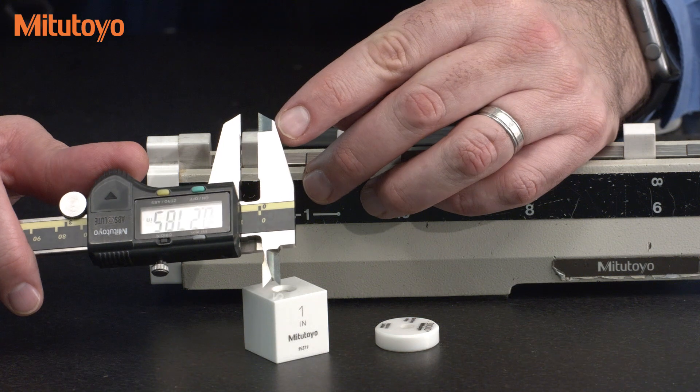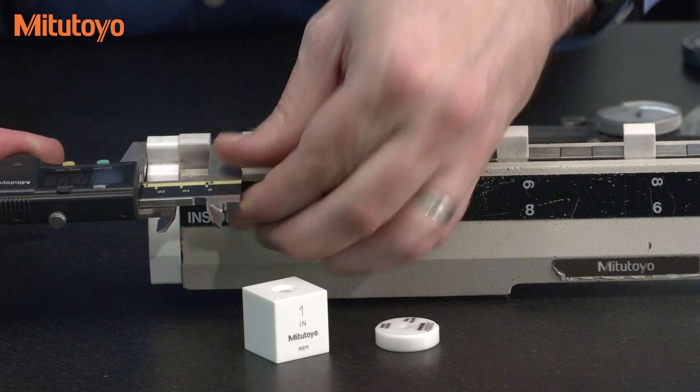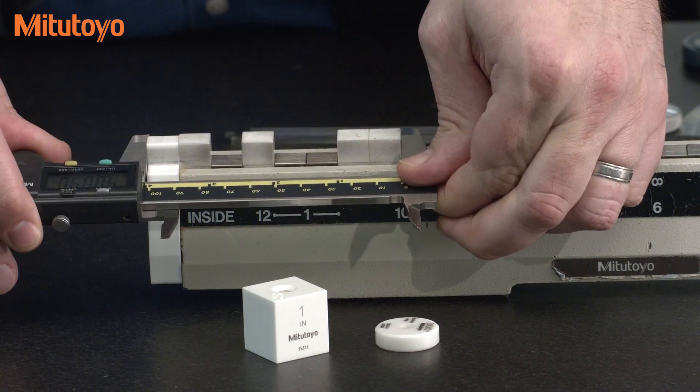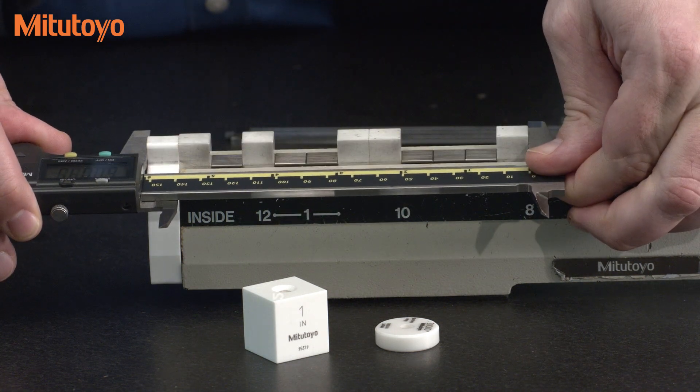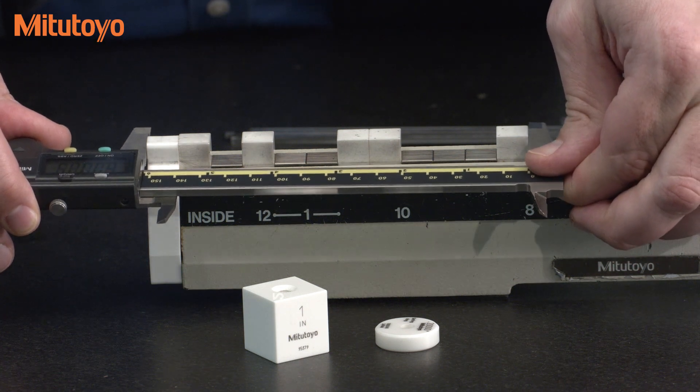For the outside jaws, we take a series of measurements over the measuring range. One inch, two inch, four inch, six inches, and we also vary where we are across the jaws.